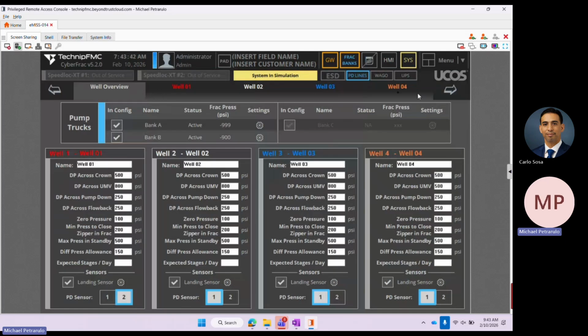So we have several tabs. We're looking at the well overview. Well overview is where you access your pump truck information. It's also where you access the set points that we use to drive all sorts of interlocks. Each of these could be explained in detail. The text is a little hard to interpret. So DP stands for delta pressure. We're saying your delta pressure across the crown valve can be no more than 500 psi.